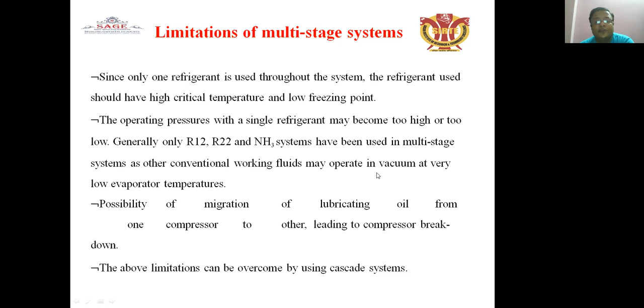There is also a possibility of migration of lubricating oil from one compressor to another, leading to compressor breakdown. The above limitations can be overcome by using a cascade system. This will be discussed in another class. These are the limitations of the multi-stage system where a single refrigerant is used. So that's why R12, R22, NH3 systems have been used in a multi-stage system, as conventional working fluids may operate in a vacuum at a very low operating temperature.